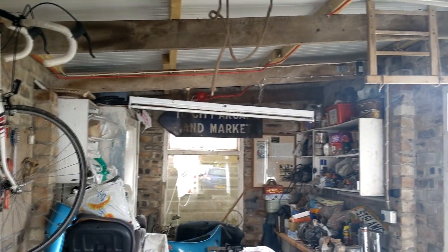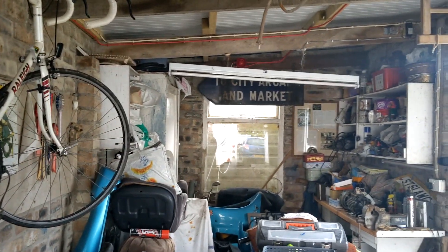I'll not reset it just yet. I'll reset it when I set it off in the garage. I'm going to test the garage call point. I'll stick around in here so you can actually hear the sounder speak its message, because this is a voice sounder in here.